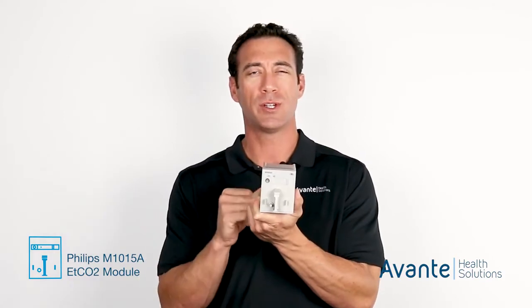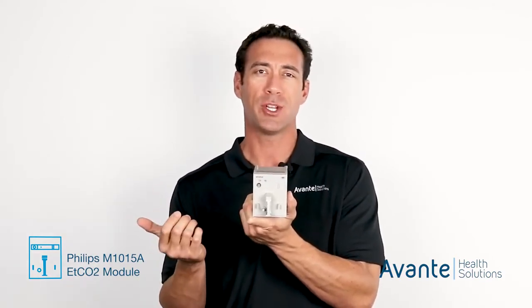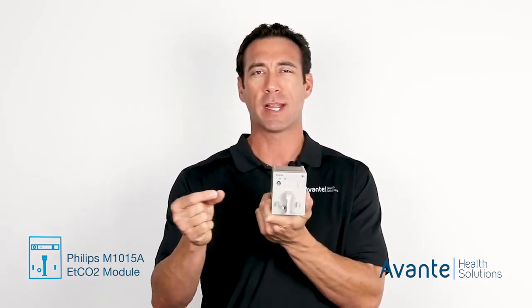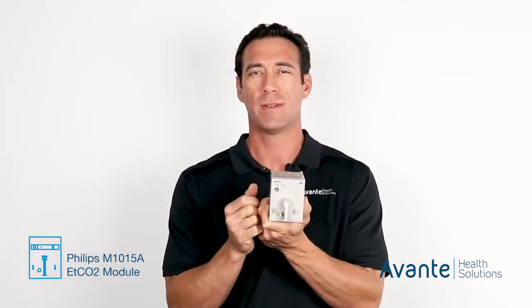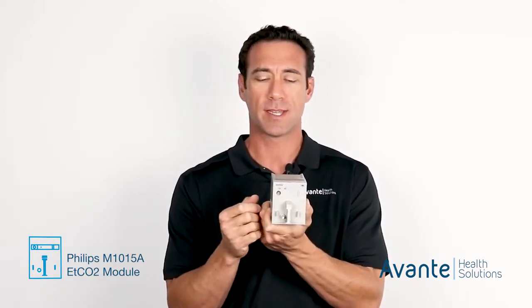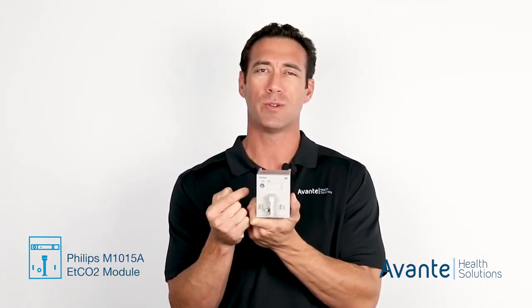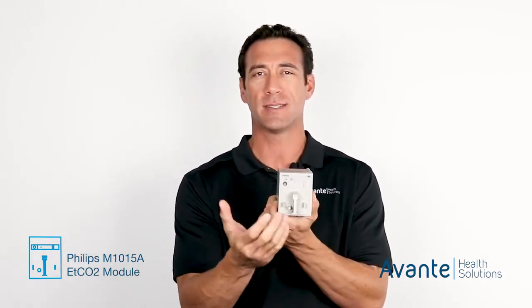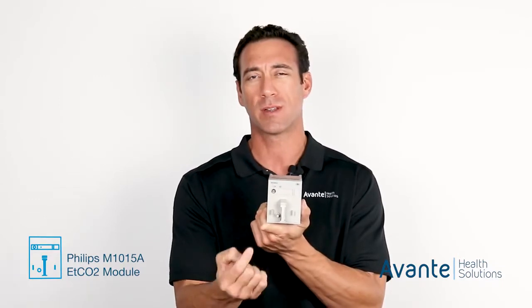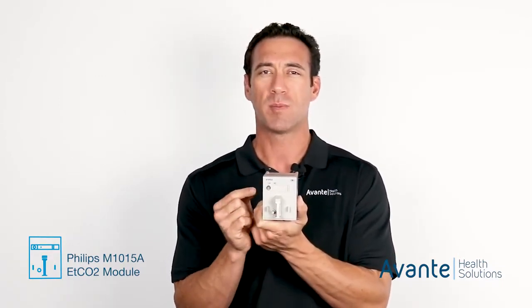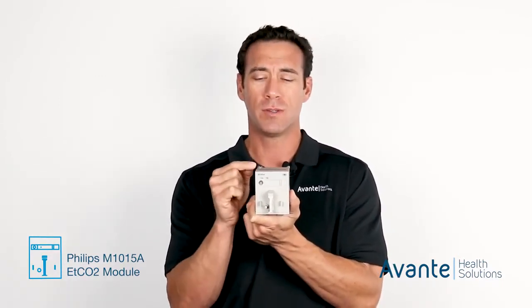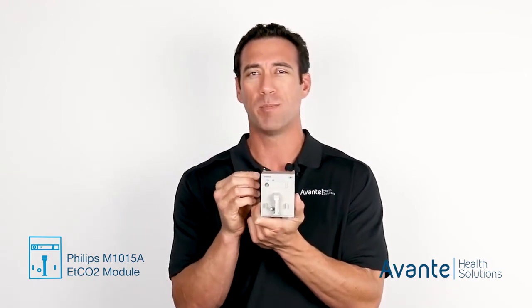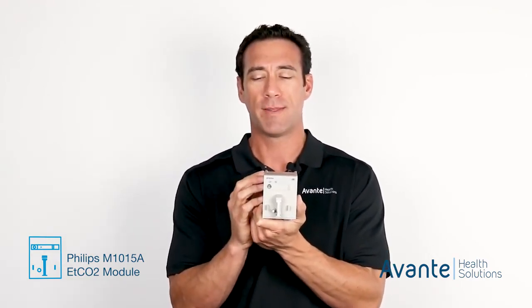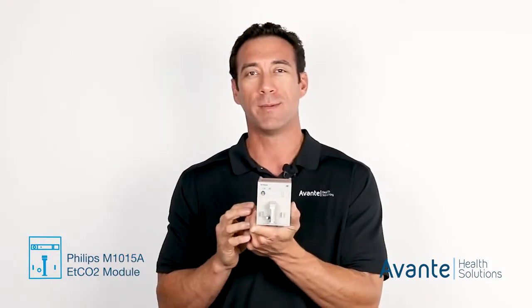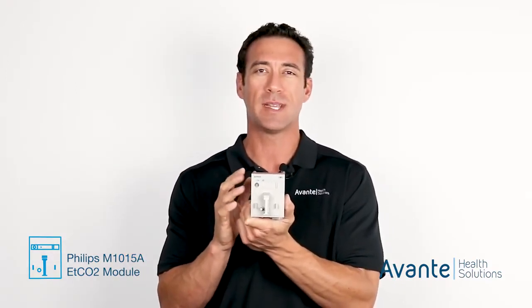So on the intubation tube that's going into an anesthetized patient, you're going to have a plug-in onto that intubation tube, and that is going to then feed right into this module. The respired gases or respired breath from the patient is going to go right into the module, and this module is going to measure CO2 using an IR or infrared bench or infrared light, and then that will be transmitted and shown on the monitor. This is going to be your Philips M1015 CO2 module.